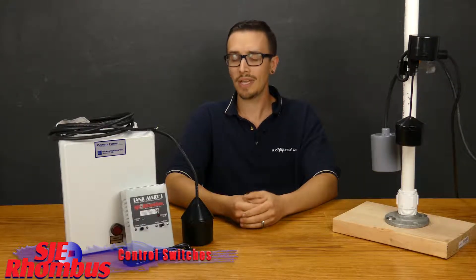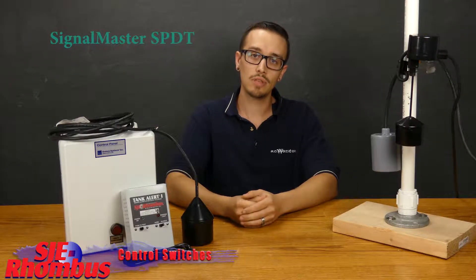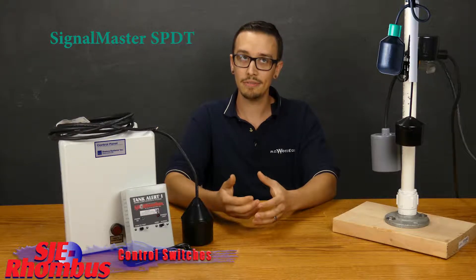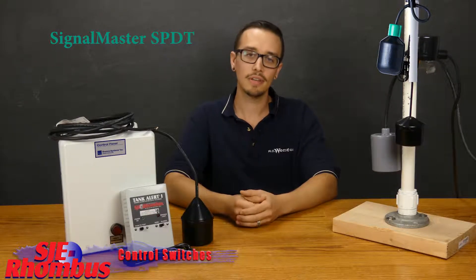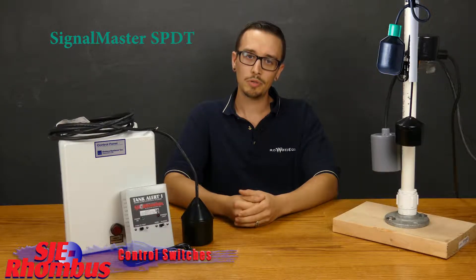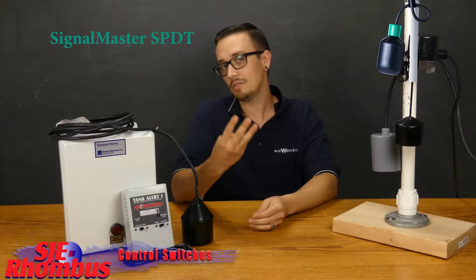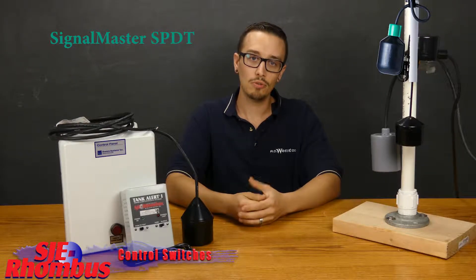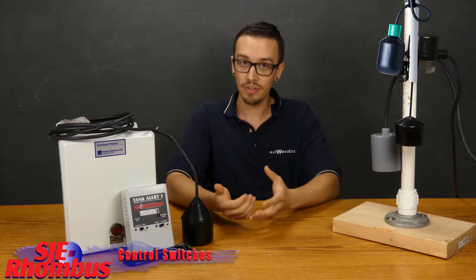In addition in their mechanical offering, they have a little bit more of a specialized offering where they offer not only normally open or normally closed, they offer what's known as a single pole double throw switch or SPDT for short. The single pole double throw switch basically is going to have three wires coming out of it: normally open, normally closed. It's a nice switch to have on your truck if you run into both normally open and normally closed switches in the field. That way you've always got the right switch for the job.